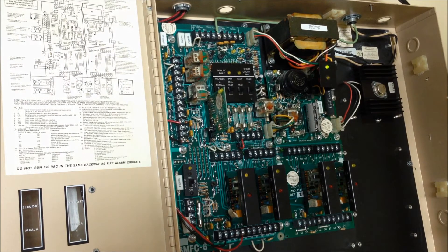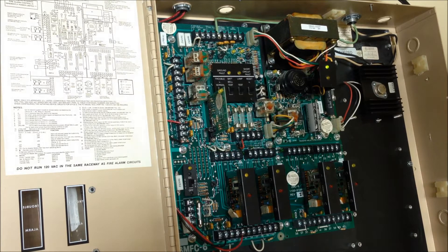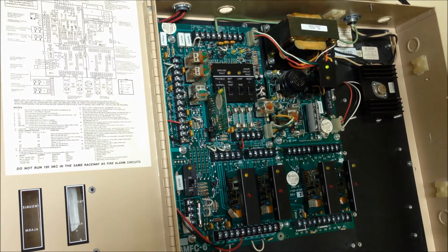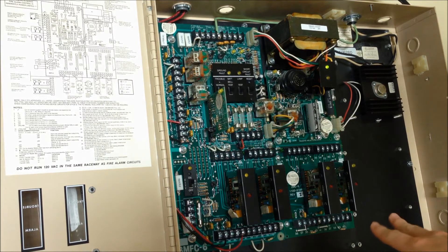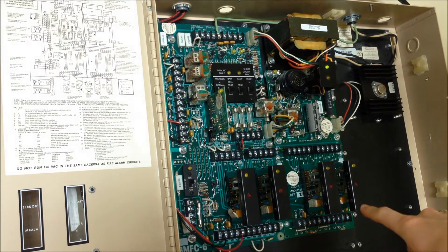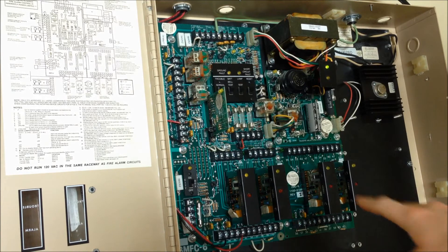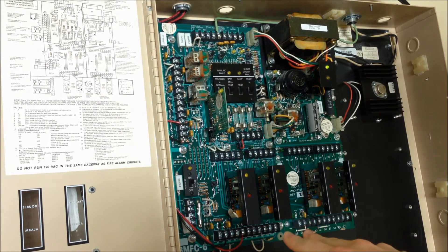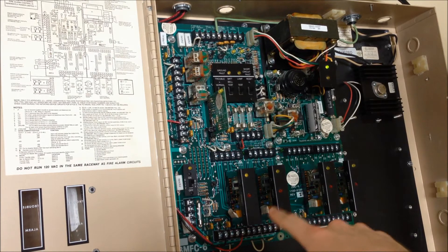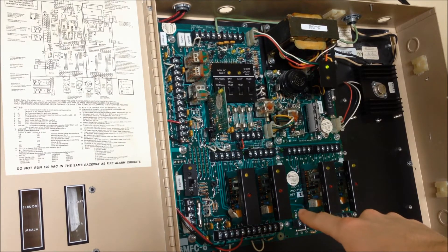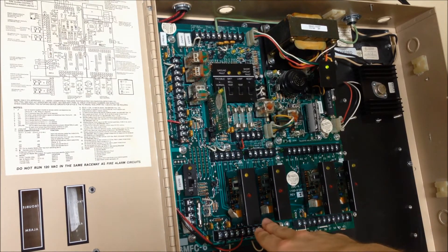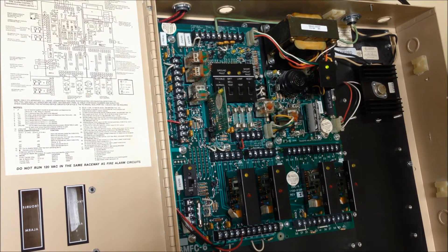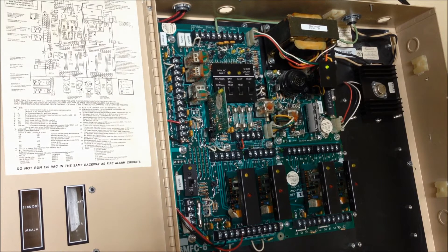So with the panel door open you can see that there's some pretty extensive circuitry in here for a small four zone panel. This is based on a modular architecture so you can see we have a two zone expansion board down here with two zone cards and then mounted on the main board of the panel the BMFC-6 board we have two additional zone cards here. The first card here zone one you can see some of the wiring running down from the little display setup I have.